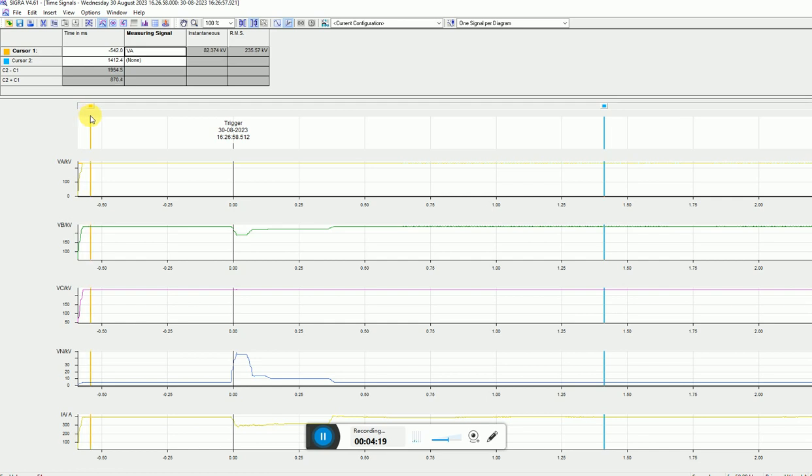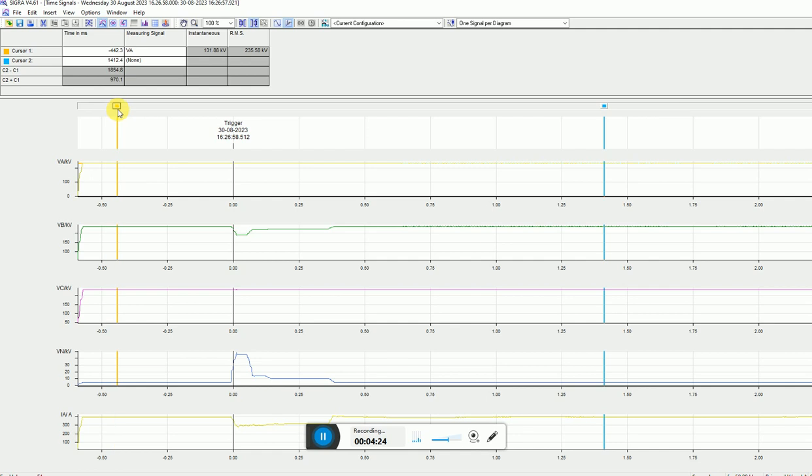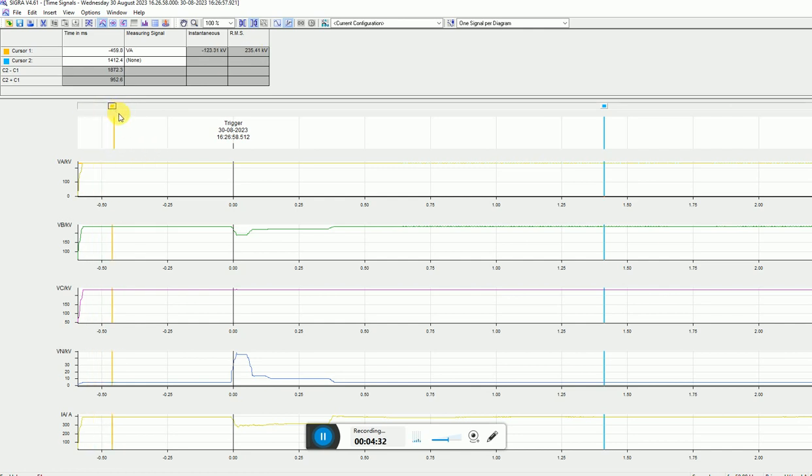You can see my voltage instantaneous and RMS. This is 400 kV line. So you can see for phase to earth VEA, for single phase voltage, this will be 235 kV. So my R phase voltage is running to 235 kV.